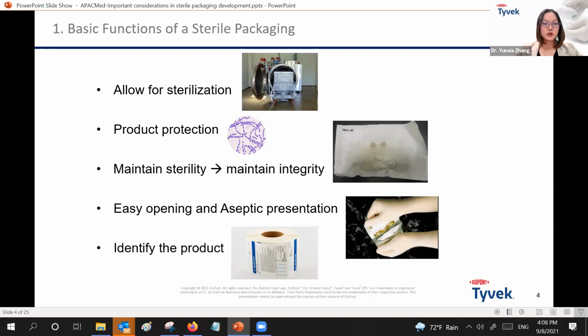And third, the sterile packaging should maintain sterility of the medical device inside till the point of use. In order to maintain sterility, it is important to maintain the integrity of the packaging during sterilization, handling, storage, and distribution till the point of use in the healthcare facility. Also, sterile packaging should allow for easy opening and aseptic presentation. This is very important because we don't want our device to be contaminated during the presentation stage. And finally, sterile packaging should be able to identify the product. In order to identify the product, sterile packaging should be able to take printing, also ensuring the traceability of the product.